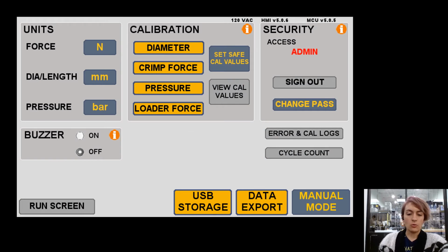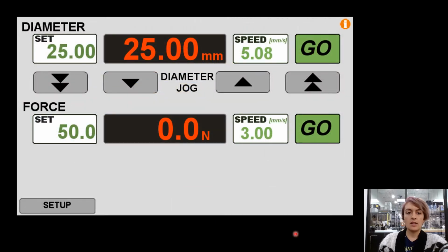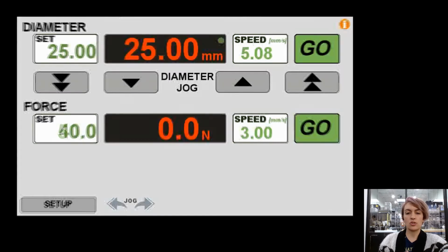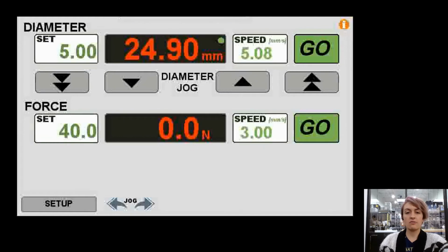For manual control, what we'll want to do is be on the setup screen here, and you can see down here there's a manual mode button. So that's what you will want to click. And then it takes you to this screen where you can enter a manual diameter and press go, or you can enter the force that you want to crimp to and press go. And then that will make the machine actually move to the diameter that you have set it to. So if I set it to 5 and I push go, then it'll start to reduce the diameter down to 5 millimeters. You can see that I get both diameter and force feedback from the machine as it's moving.